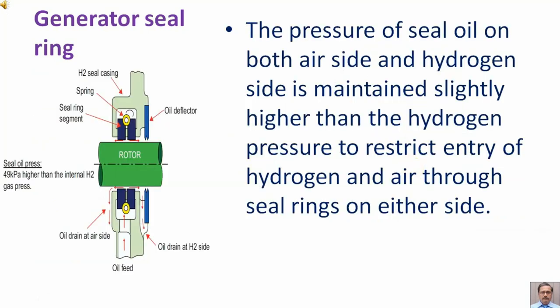The pressure of the seal oil on both the air side and the hydrogen side is maintained slightly higher than the hydrogen pressure, to restrict entry of hydrogen and air through the seal rings on either side.